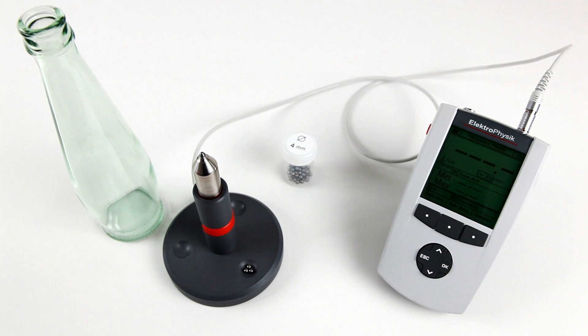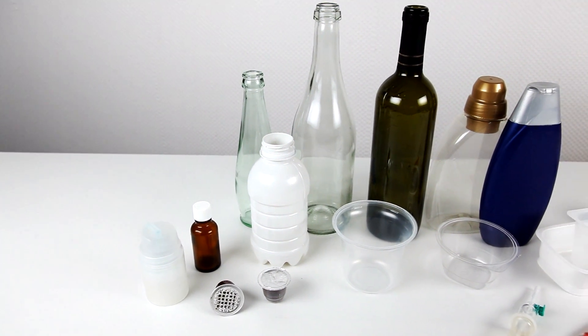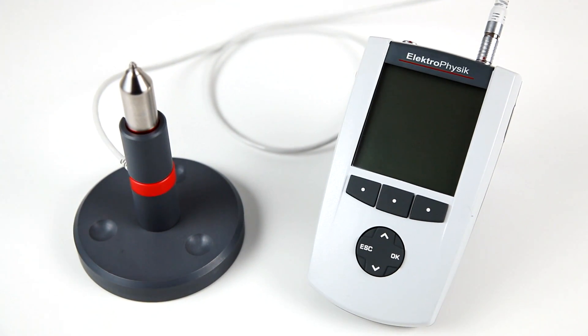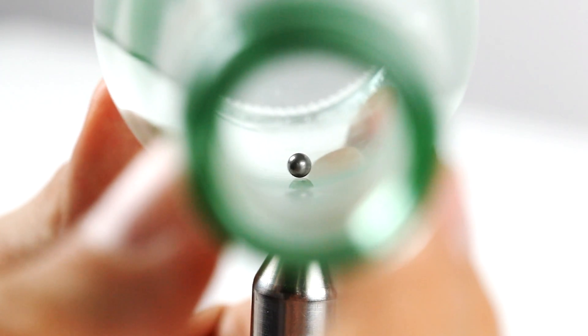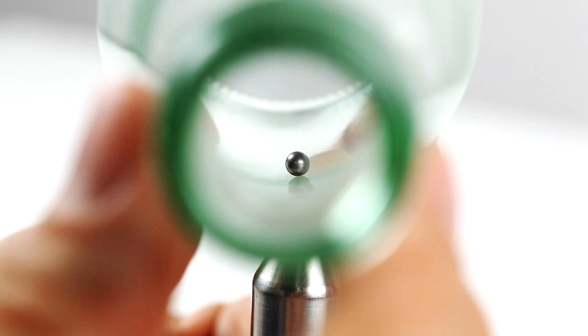The MiniTest FH series made by ElektroPhysik Germany offers the ideal solution for wall thickness measurement of all kinds of hollow parts made of non-magnetic material. MiniTest FH works on the magnetostatic principle using a steel ball or a magnetic ball as reference.